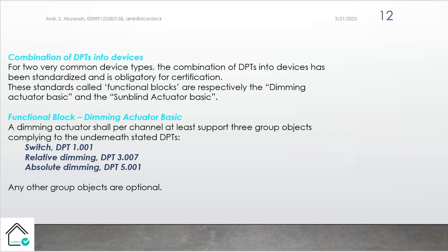Combination of DPTs into devices. For two very common device types, the combination of DPTs into devices has been standardized and is obligatory for certification. These are standardized and called functional blocks. As I said, we should put different group objects together to make some specific operation, like dimming or a blind actuator.